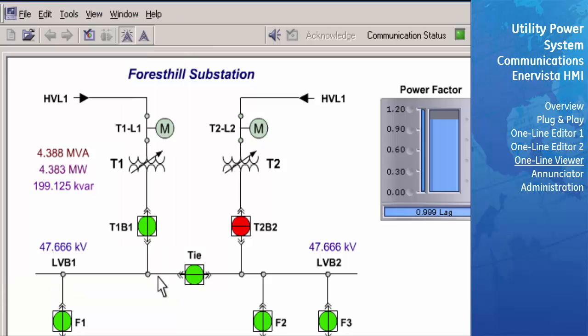Control. In this schema, there are 6 manual indication controlled breakers whose states are manually set in the viewer. There is also 1 automatically controlled breaker whose state changes automatically within the viewer to reflect the value on the device. Finally, there is 1 control breaker whose state is changed on the physical device via commands sent from the System Viewer. This state change is also automatically reflected in the viewer. We will now go through the steps on how to utilize these various types of breakers.